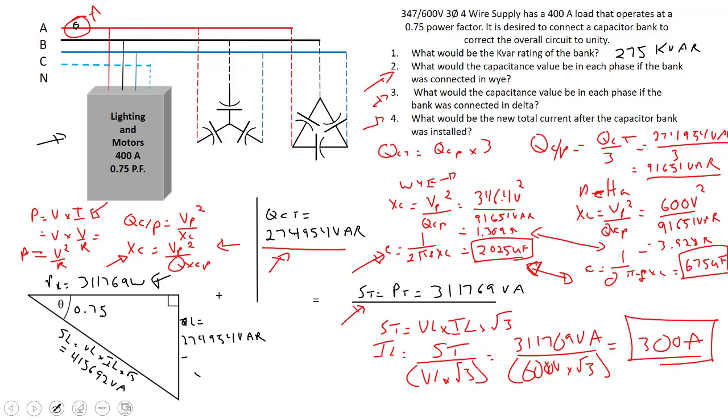Not bad. By correcting this circuit to unity, we have dropped the current down basically 100 amps from where we started. That's pretty good, that's a lot of current. Hopefully this helps out, we're going to see you on the next one.